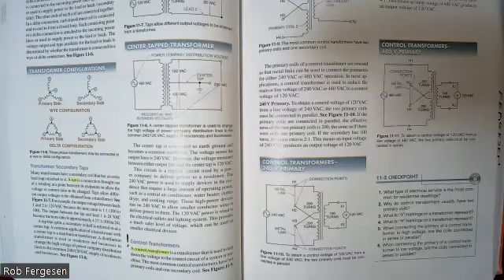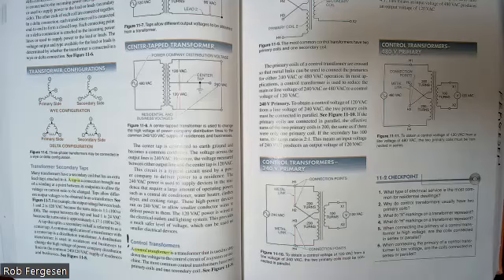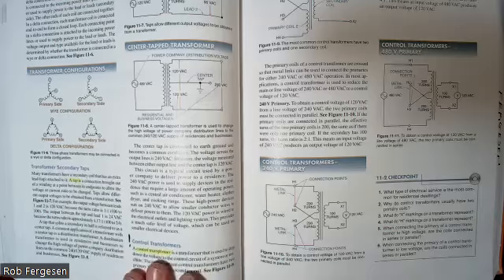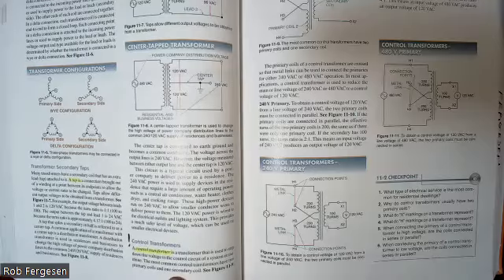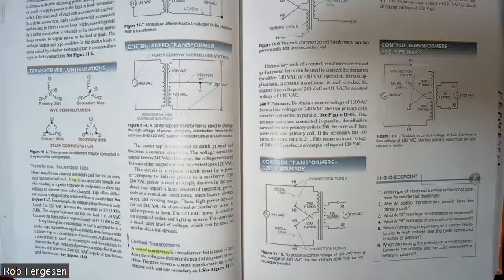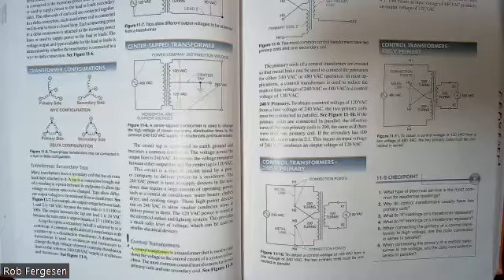And so inside the machine, I will use what's called a control transformer to convert that massive voltage coming out of that three-phase power down to a single phase 120, or single phase 120 down to a DC voltage to use as the control power, the low voltage power that I can run through my switches and my indicator lights and my coils and things like that. So that control stuff, that on off, that switch, those indicator lights, all that stuff needs a lower voltage.